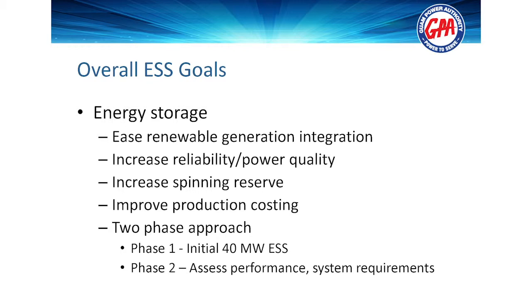Want to increase reliability and the power quality. Want to increase spinning reserve. Spinning reserve in an islanded utility is a huge component of cost. And as you add renewables, that spinning reserve cost can actually increase a lot. And so one of the things that GPA wanted to do was be able to decrease its spinning reserve costs while at the same time adding renewables. They wanted to improve production costing. And we looked at this as a two-phase approach. We looked at it initially as a 40 megawatt energy storage project, and then the second phase was trying to see what our performance assessment and system requirements were. Okay, next.